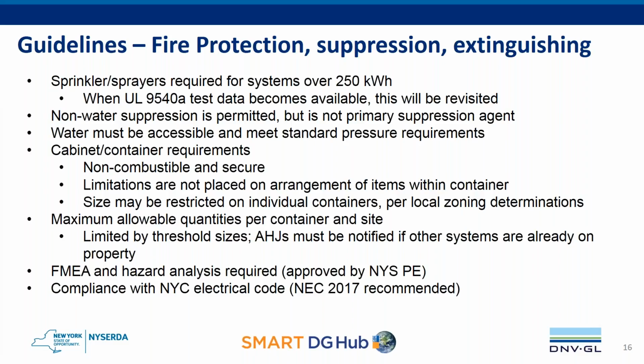The requirements, as noted in the checklist, are limited by threshold sizes. So for instance, a 20 kWh system, if it were to be connected to another 20 kWh system for a full rating of 40 kWh, would be considered in the next threshold size, so the medium threshold size. If there is already an energy storage system on site, for instance, if two residents in a high-rise unit are both looking to install 20 kWh systems that are not planned to be interconnected, the FDNY and DOB must be notified that there is another system already on the property, but it does not bump it up into the next threshold size.